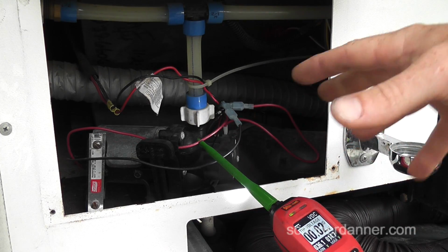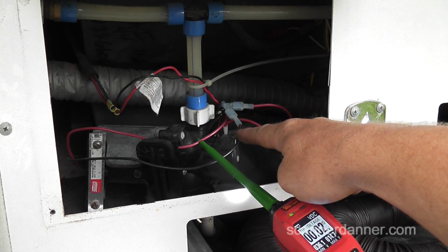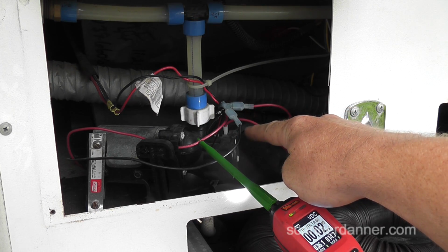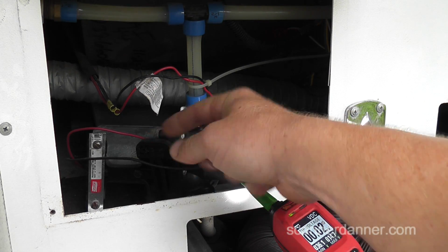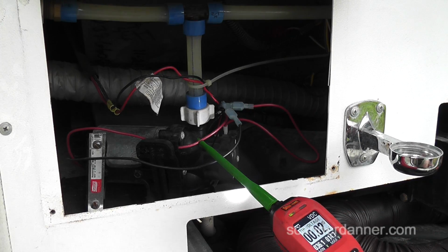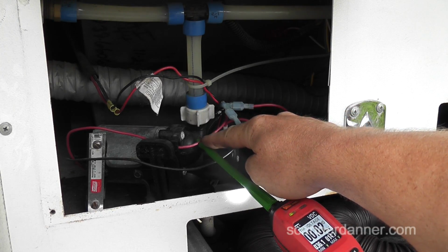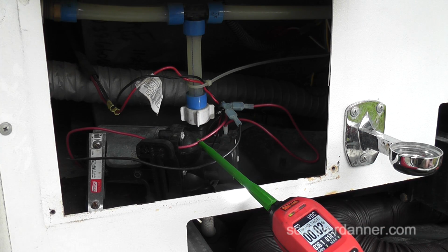With low water pressure, that switch over here should maintain a closed position. We should send direct 12 volts to the motor all the time. And with low water pressure, that's not what we were seeing. I was having low voltage here. This is not a bad pump. It's not a bad pump.